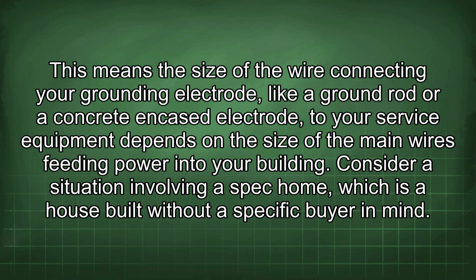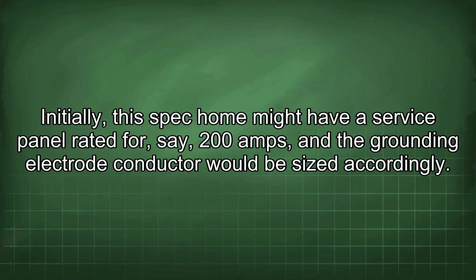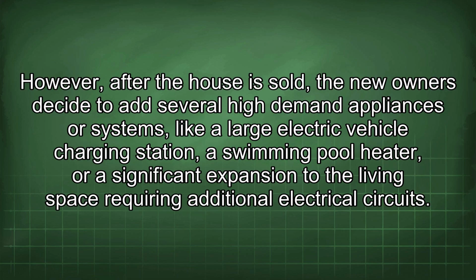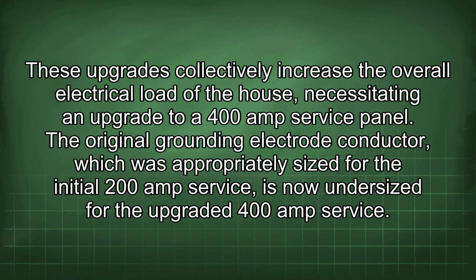Consider a situation involving a spec home, which is a house built without a specific buyer in mind. Initially, this spec home might have a service panel rated for, say, 200 amps, and the grounding electrode conductor would be sized accordingly. However, after the house is sold, the new owners decide to add several high-demand appliances or systems like a large electric vehicle charging station, a swimming pool heater, or a significant expansion to the living space requiring additional electrical circuits. These upgrades collectively increase the overall electrical load of the house, necessitating an upgrade to a 400 amp service panel. The original grounding electrode conductor, which was appropriately sized for the initial 200 amp service, is now undersized for the upgraded 400 amp service.